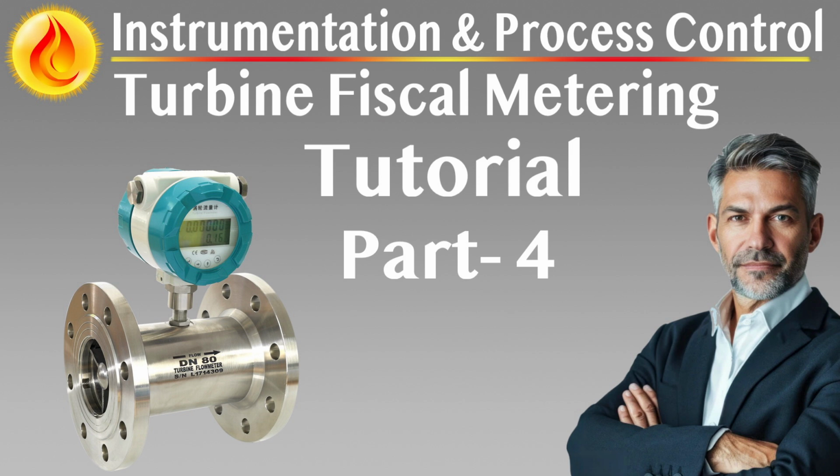The Prover microcomputer must initiate and control the entire proving sequence. This includes receiving a proving command, automatic, semi-automatic, or manual, checking system readiness, and initiating sphere launch or flow reversal based on current valve positions, flow rate stability, and process conditions. It must verify that prover inlet and outlet temperatures and pressures are within allowable limits before commencing a run.